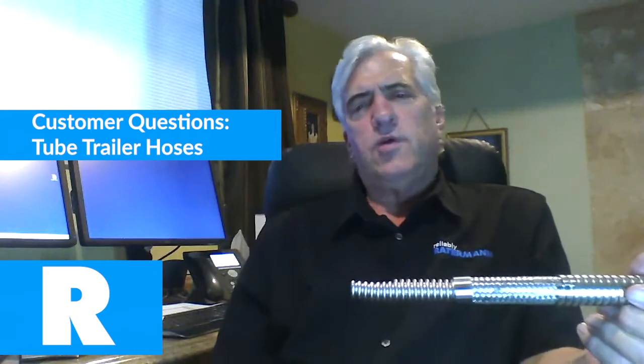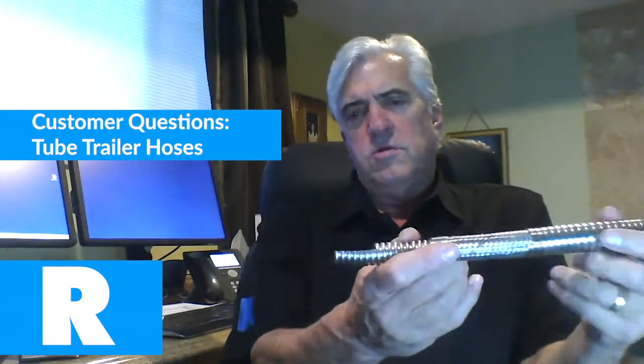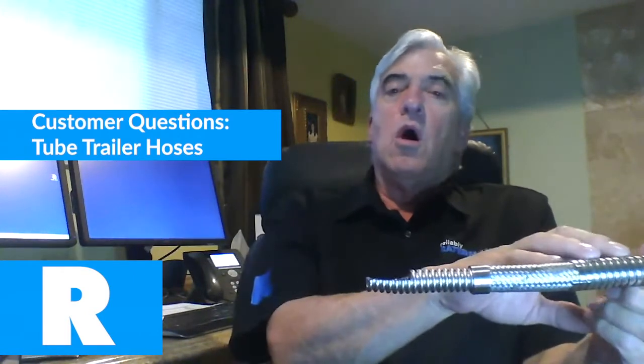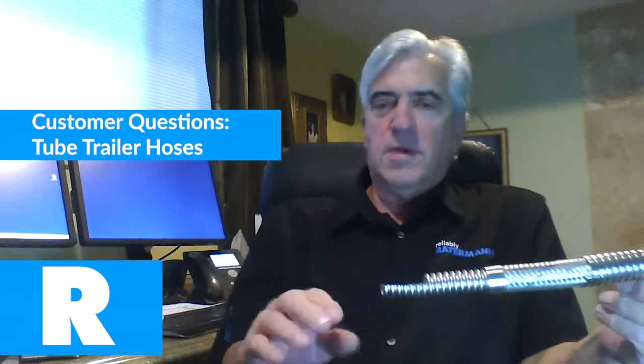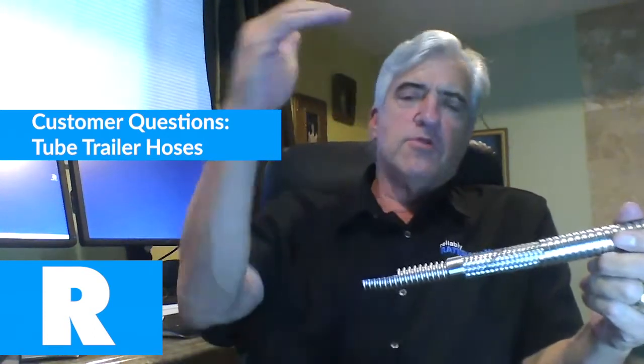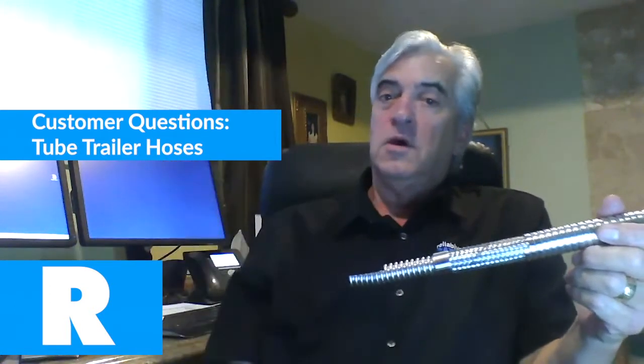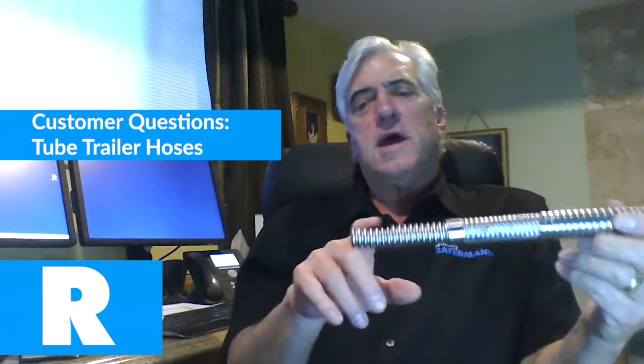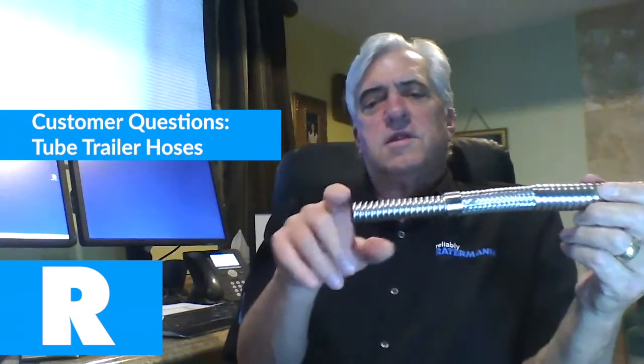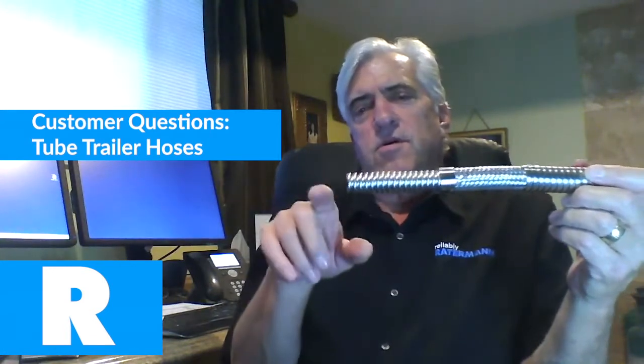But what about tube trailer applications? If you were to take this hose and use it in a tube trailer application, it would work okay at first. But as your flow rate increases and it exceeds a certain threshold, which is 150 feet per second, what happens is it establishes a resonant frequency inside the crown of the corrugation. That's the part that's curved.